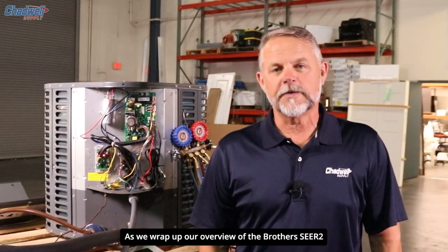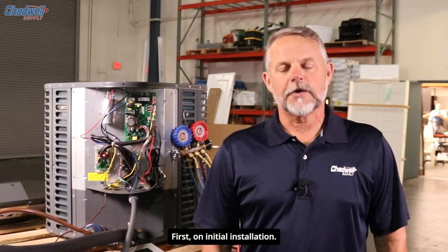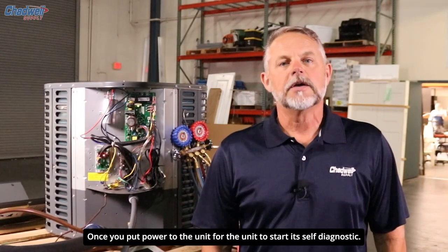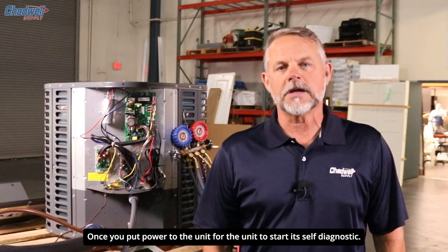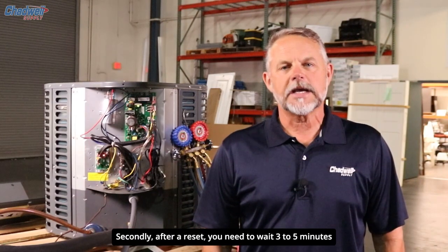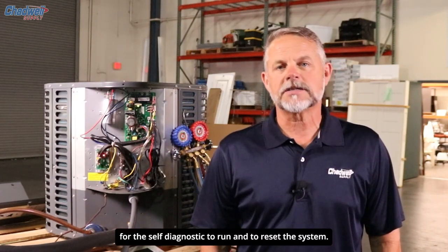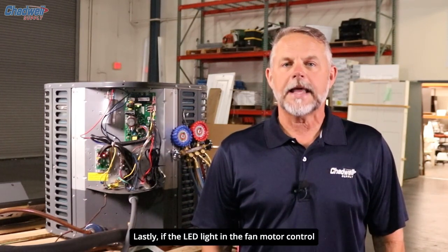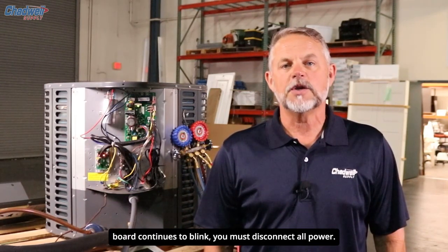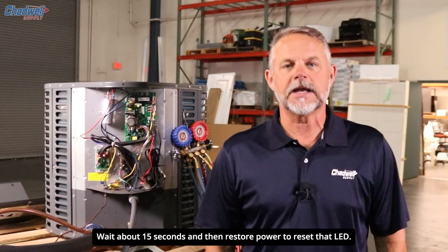As we wrap up our overview of the Brothers SEER2 unit, there are three important takeaways. First, on initial installation, wait 15 to 20 seconds once you've applied power for the unit to start its self-diagnostic — the compressor will start first, then the fan motor will come on after. Secondly, after a reset, wait 3 to 5 minutes for the self-diagnostic to run and reset the system. Lastly, if the LED light on the fan motor control board continues to blink, you must disconnect all power, wait about 15 seconds, and then restore power to reset that LED.